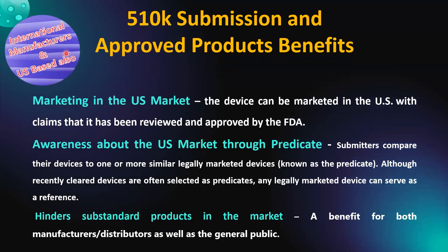Whether you are an international manufacturer of a medical device or have a manufacturing facility in the United States of America, 510-K approved products have several benefits. First, marketing in the U.S. market — the device can be marketed in the U.S. with claims that it has been reviewed and approved by the FDA. Second, awareness about the U.S. market through predicate — submitters compare their devices to one or more similar legally marketed devices known as the predicate, and any legally marketed device can serve as a reference. Third, it hinders substandard products in the market, which is a benefit for both manufacturers/distributors as well as the general public.